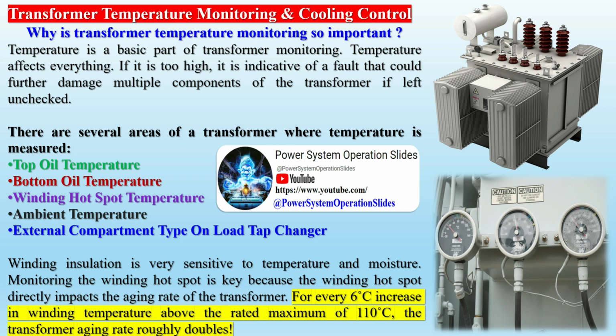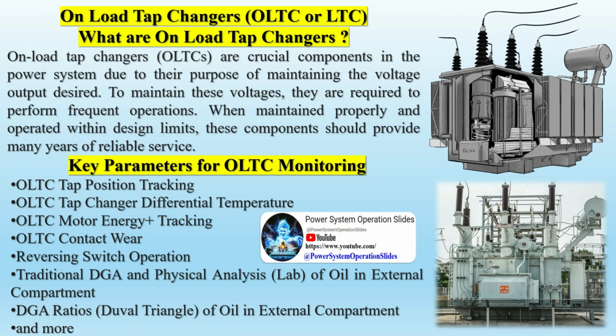Oil temperature sensor. While inspections by personnel are conducted at longer intervals, the oil temperature sensor constantly monitors the transformer for any rise in oil temperature, and any internal or cooler abnormality can be effectively detected. Oil level monitoring sensor. While visual inspections are conducted at longer intervals, the oil level monitor can detect leakage from the transformer more effectively.